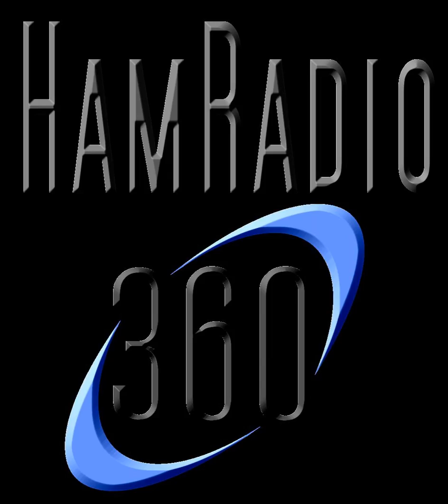That's a great question. What I'd recommend is, if the scope has a probe or is being sold with probes, connect the probe up to the probe compensation or calibrator output on the scope. That's there to properly compensate a 10x probe. Hook up to that and make sure you can see that square wave on the scope. Adjust the horizontal time base all the way to the slowest and all the way to the fastest to be sure that you get a sweep in every one of those positions, that you don't have a problem with the switch going forward. Adjust the vertical control when you're hooked up to the calibrator to be sure that the signal is indeed increasing or decreasing in size as you change that vertical scale. Make sure that there aren't any dead spots in that.